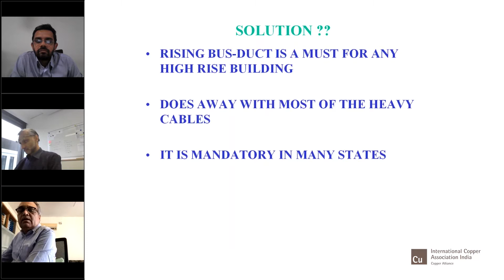In many states where you must have been associated with works, especially the southern states, it has now been made mandatory by the electrical inspectorate, what they call CEIG there, that they don't allow any high-rise building with cables going the way I showed in the duct. All the vertical cables have to be in the form of a rising bus duct. But yet there are people who are not following this.